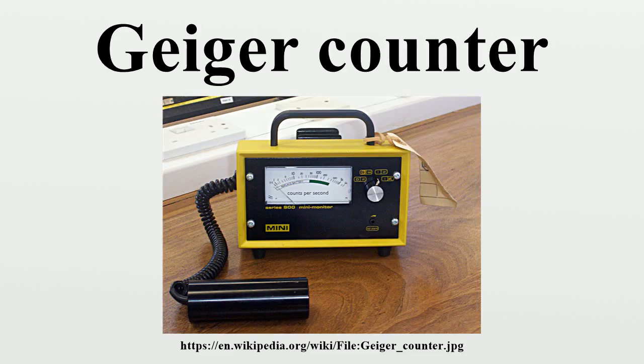For high-energy gamma, it largely relies on interaction of the photon radiation with the tube wall material, usually 1 to 2 mm of chrome steel on the thick-walled tube, to produce electrons within the wall which can enter and ionize the fill gas. This is necessary as the low-pressure gas in the tube has little interaction with high-energy gamma photons. However, for low-energy photons there is greater gas interaction and the direct gas ionization effect increases. With decreasing energy, the wall effect gives way to a combination of wall effect and direct ionization, until direct gas ionization dominates. Due to the variance in response to different photon energies, windowless tubes employ what is known as energy compensation, which attempts to compensate for these variations over a large energy range.